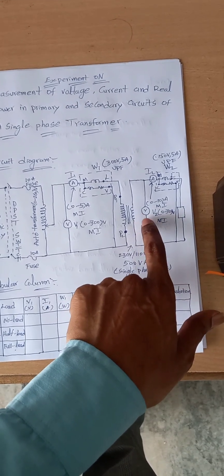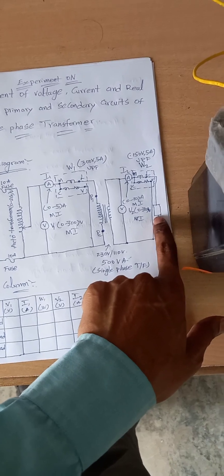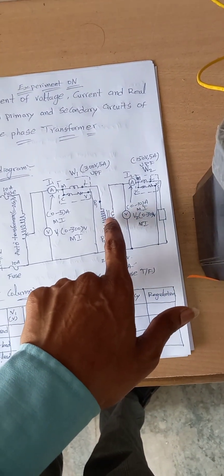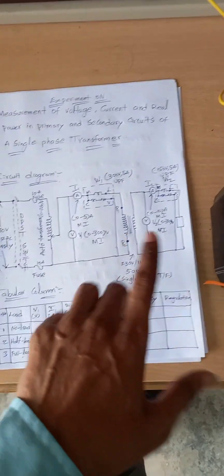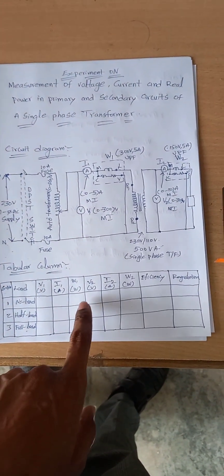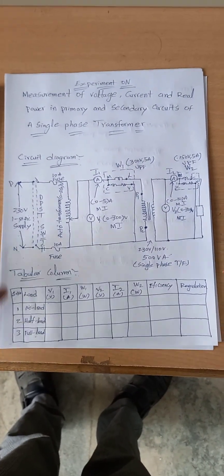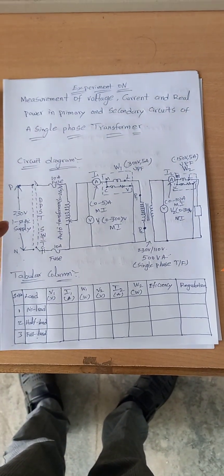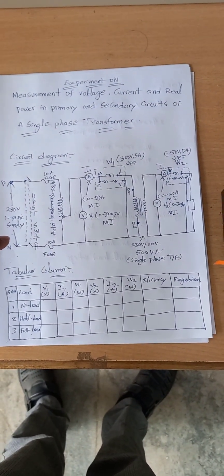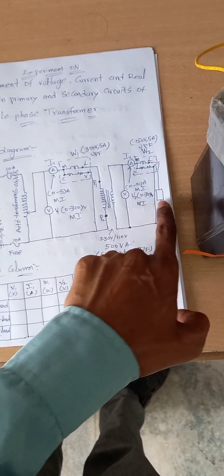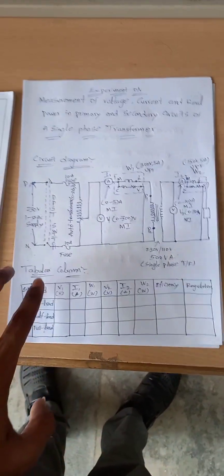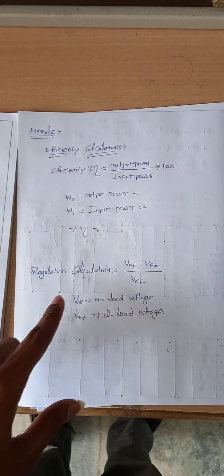In the load test we connected the voltmeter across the load only. But here we are going to measure the secondary side voltage, current, and power, so we are connecting the voltmeter across the secondary winding — that's it. Other than that, everything else is the same. The tabular column is also the same: no load condition, half load, full load, and V1, I1, W1, V2, I2, W2, efficiency, and regulation. The only difference compared to the load test is the voltmeter placement — there we connect it across the load and here we connect it across the secondary winding.